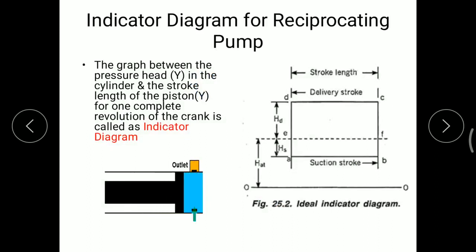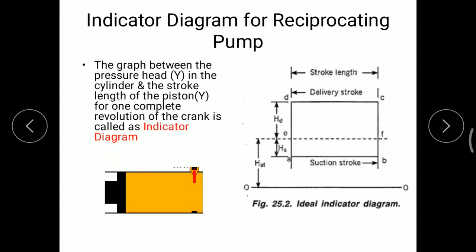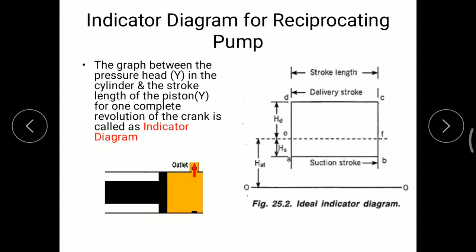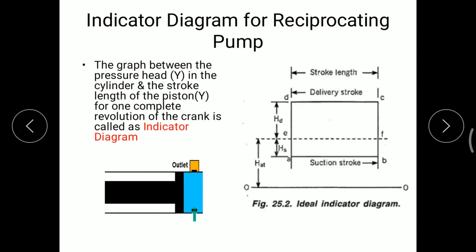Now we will see the indicator diagram for a reciprocating pump. The graph between pressure head in the cylinder and stroke length of the piston for one complete revolution of the crank is called an indicator diagram. When the piston moves from top dead center towards bottom dead center, the crank covers 0° to 180° rotation. When the piston moves from bottom dead center towards top dead center, the crank rotates from 180° back to 0°, completing one full revolution, during which the pressure in the cylinder increases.